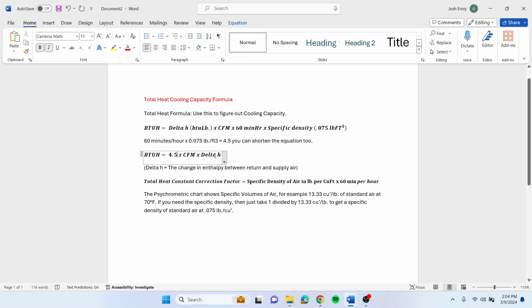The reason you're checking that is because you're actually doing latent heat removal when you're doing cooling. You're typically dehumidifying that air. So you need to know what's the total heat that you got rid of versus just sensible heat. Like say you just went from 2 degrees to 4 degrees, well, you know that's 2. Well, when you're getting rid of latent heat, that's not the same as sensible heat.